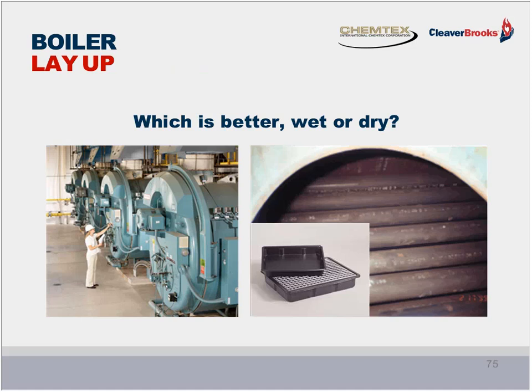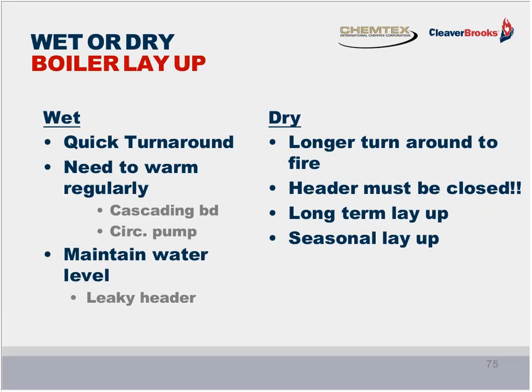But which one's better, wet or dry storage? Well, every facility is a little bit different, and every application is a little bit different, and you need to take a look at it. Wet layup allows for quick turnaround, but you need to warm the boiler regularly to make certain that you're circulating the water, or put a cascading blowdown system in or a circulating pump. You can ask your water treatment provider about that.